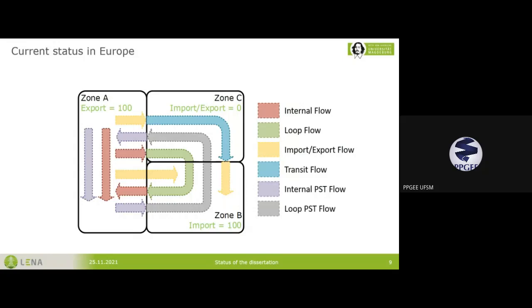And if, for example, wind power in Germany feeds into a load in Czech Republic, and the power flow goes through Poland, we have a transit flow. So these are the typical market flows that we have here, and additionally, other equipment in the grid, such as HVDC links and phase shifting transformers, will produce additional flow types. So you can have internal phase shifting transformer flows. This is when the phase shifting transformer is located in the same zone as the line you're looking at, and you have loop phase shifting transformer flows. Because the phase shifting transformer produces a cycle flow every time, it will also interact with lines that are in parallel zones of the transformer.